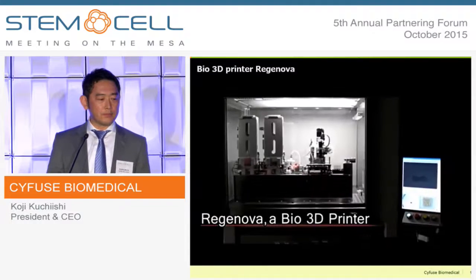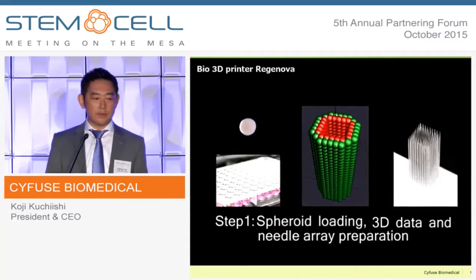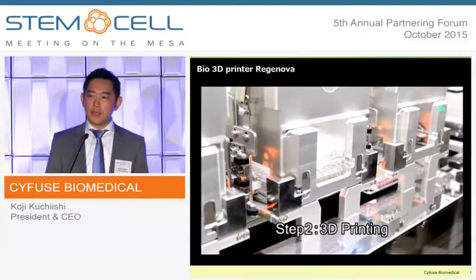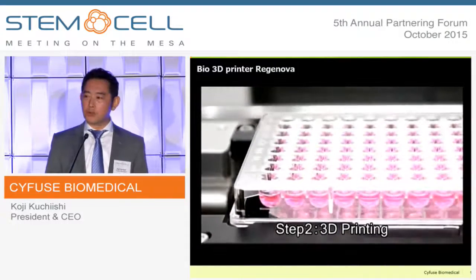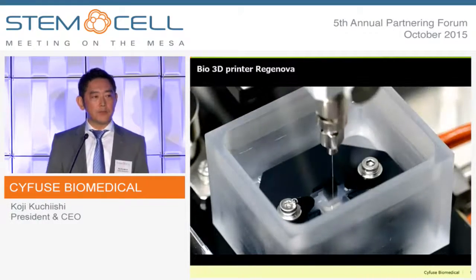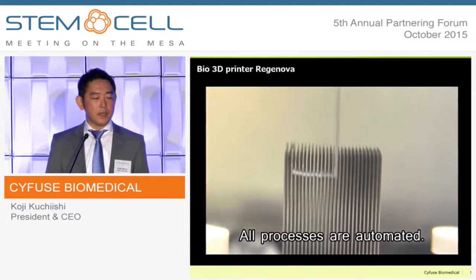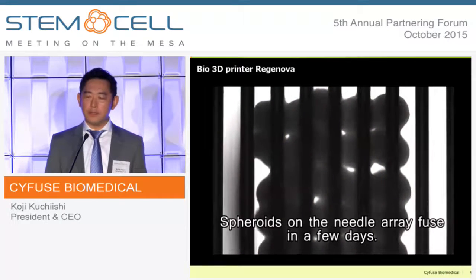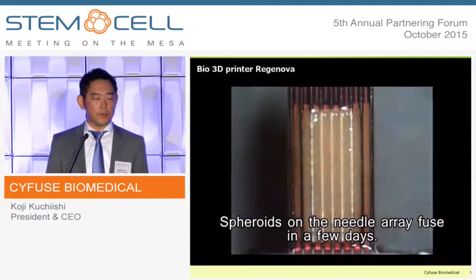Let's take a look at the video. This machine is basically a pick-and-place machine, picking up spheroids and placing them in the needle array according to the data. The printing process is precisely controlled with machine vision. The minimum pitch of the system is 300 micrometers. The mounted cell aggregates look like a baby cone, and they fuse together in a few days.